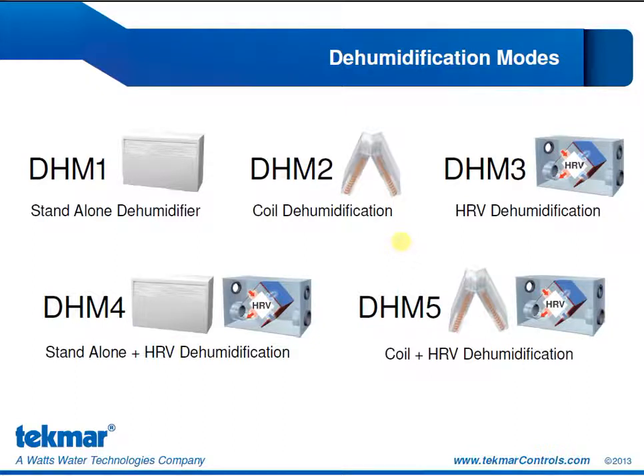Dehumidification mode 3 uses an HRV, and it exchanges stale indoor air with fresh outdoor air. It only works to dehumidify the air if the outdoor air is colder and drier than the indoor air. And this happens, as we discussed earlier, if the outdoor temperature is at least 5 degrees below the indoor dew point. So typically this kind of condition is only present in the winter. It will not address moisture problems during other times of the year.